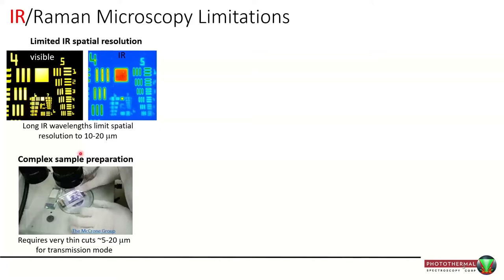There's also the issue of complex sample preparation. For infrared, the best quality spectra are typically obtained in transmission mode through thin sections — thin cuts — where sample thickness needs to be in the order of 5 to 20 microns. And there are some things you just cannot cut or are very difficult to cut.